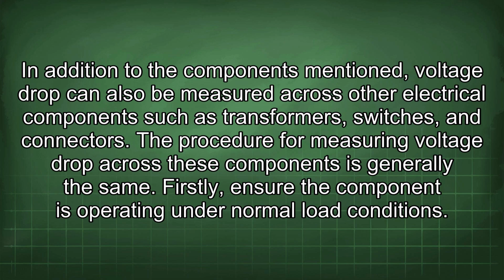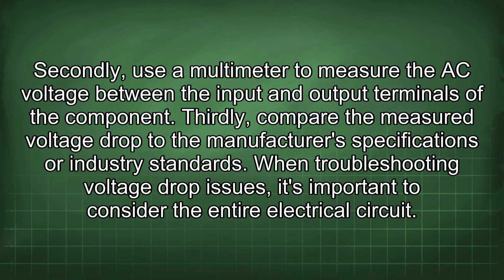Firstly, ensure the component is operating under normal load conditions. Secondly, use a multimeter to measure the AC voltage between the input and output terminals of the component. Thirdly, compare the measured voltage drop to the manufacturer's specifications or industry standards.